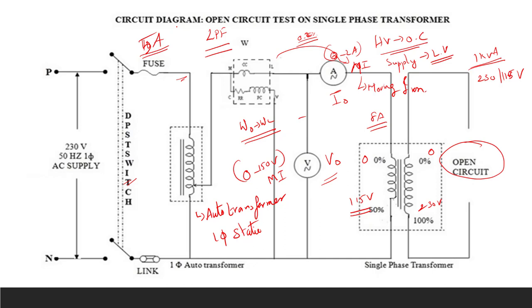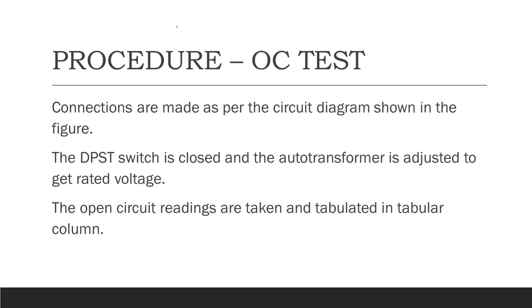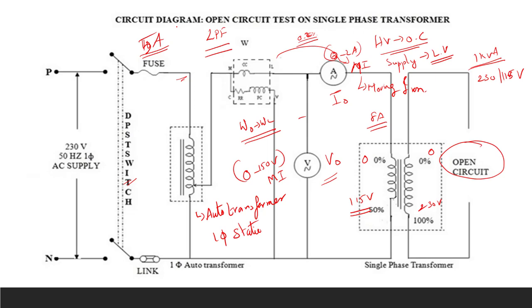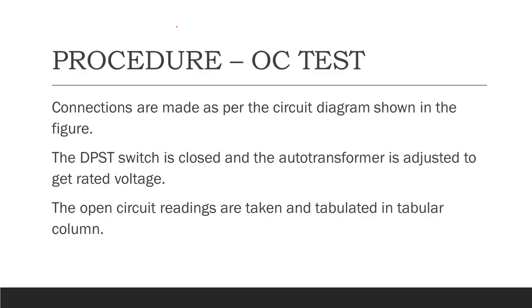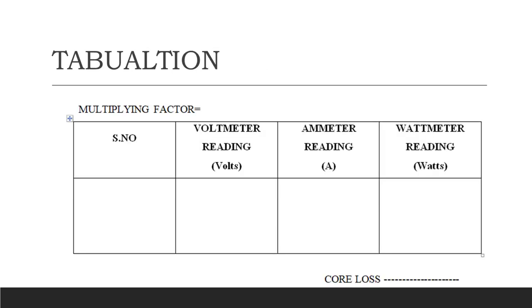This is the open circuit test for the single-phase transformer. The procedure: close the switch and set the rated voltage. From the rated voltage, find the corresponding readings from the voltmeter, ammeter, and wattmeter. In the wattmeter, the actual reading is the product of the measured reading and the multiplication factor. The actual reading will be the core loss value — this is the tabulation for the open circuit test.